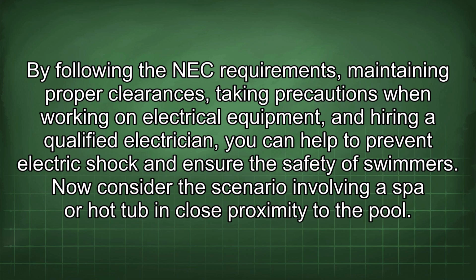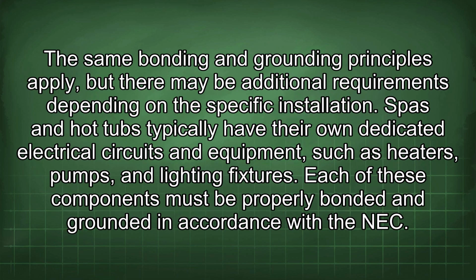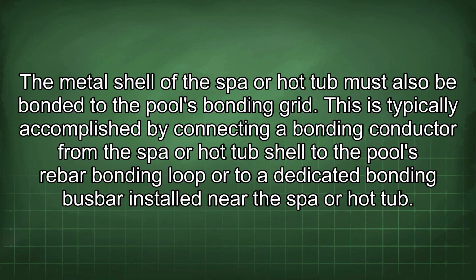Now consider the scenario involving a spa or hot tub in close proximity to the pool. The same bonding and grounding principles apply, but there may be additional requirements depending on the specific installation. Spas and hot tubs typically have their own dedicated electrical circuits and equipment, such as heaters, pumps, and lighting fixtures. Each of these components must be properly bonded and grounded in accordance with the NEC. The metal shell of the spa or hot tub must also be bonded to the pool's bonding grid.